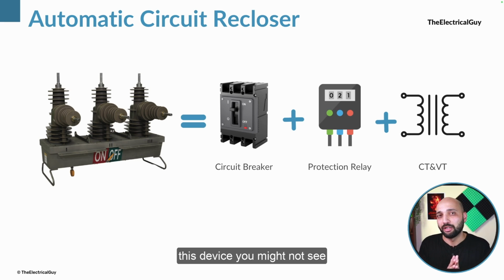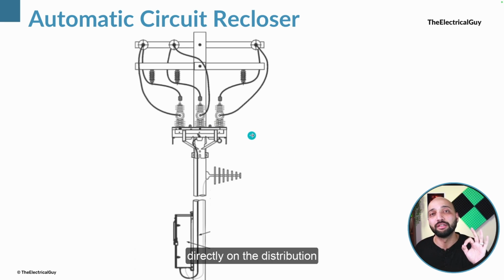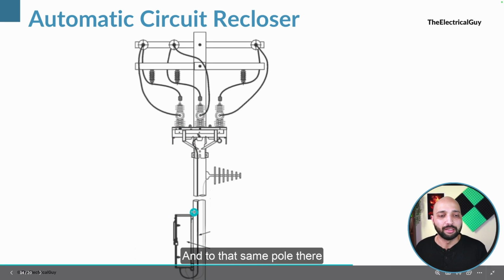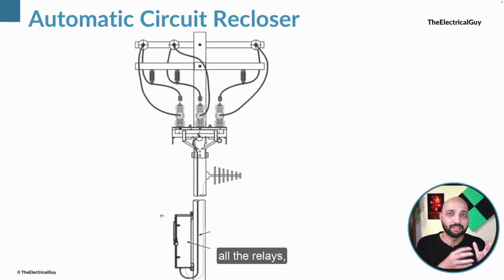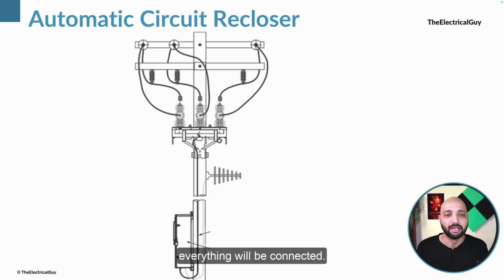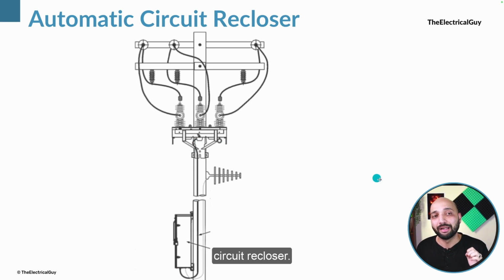Now this device you might not see very frequently here in India, but it is very widely used in different countries. And also the advantage of this device is that it can be mounted directly on the distribution pole. So here you can see the image. It is mounted directly on the distribution pole, and to that same pole there is a box connected which is a control box. Basically it will have all the relays, all the control circuitries, and everything will be connected. From here it will get input to open and close like that, right? So that is automatic circuit recloser.